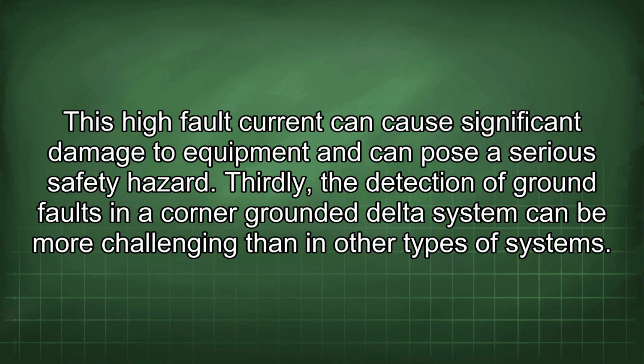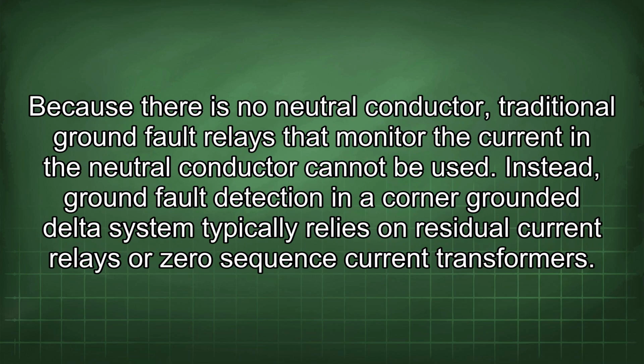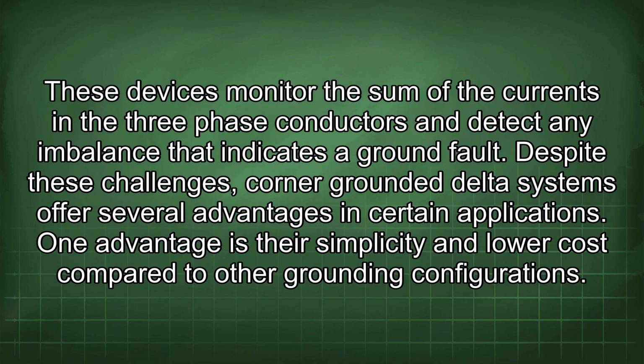Thirdly, the detection of ground faults in a corner-grounded delta system can be more challenging than in other types of systems. Because there is no neutral conductor, traditional ground fault relays that monitor the current in the neutral conductor cannot be used. Instead, ground fault detection in a corner-grounded delta system typically relies on residual current relays or zero-sequence current transformers. These devices monitor the sum of the currents in the three-phase conductors and detect any imbalance that indicates a ground fault. Despite these challenges, corner-grounded delta systems offer several advantages in certain applications.